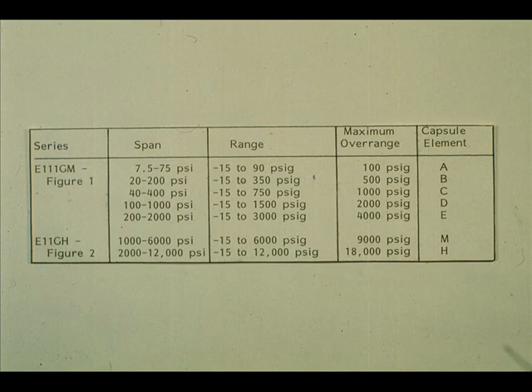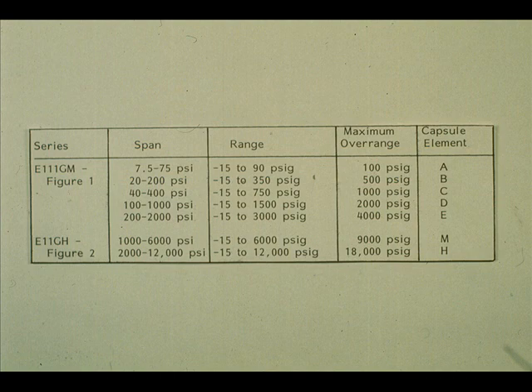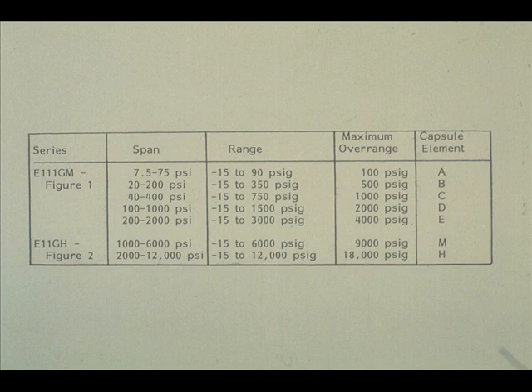Table 1 shows the various spans, ranges, maximum overrange, and required elements for particular conditions. The five capsules, A through E, are interchangeable for the E111GM. From the table, it is evident that overlapping is provided between the spans and ranges.